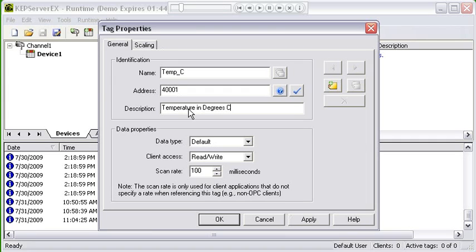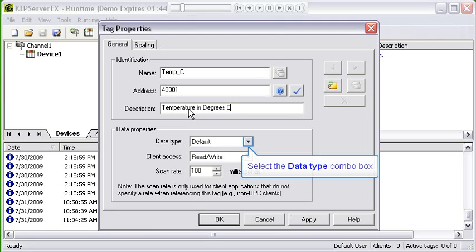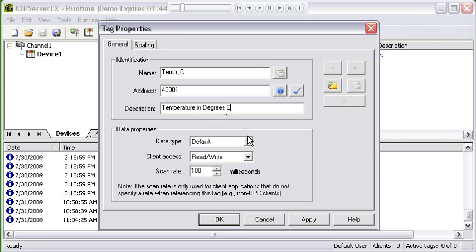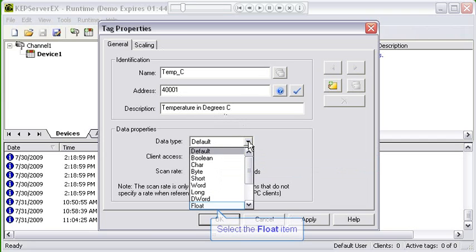The default data type for Modbus holding registers is a word data type. This is a temperature in float, so I need to change that default and select float.